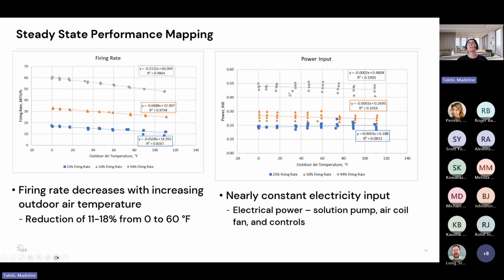And then looking at the power input. This is essentially trying to understand whether there is any large power discrepancy, any large fluctuation or large load demand, given that this is mainly a GHP unit, but there are some electrical demands corresponding to the unit itself. We see that it's minimal in this case. It's almost negligible, nearly constant. A lot of the electrical power is going to come from the solution pump, the air coil fan, and any other controls.